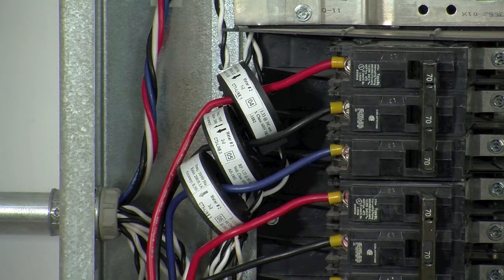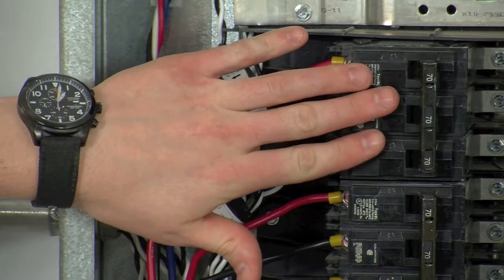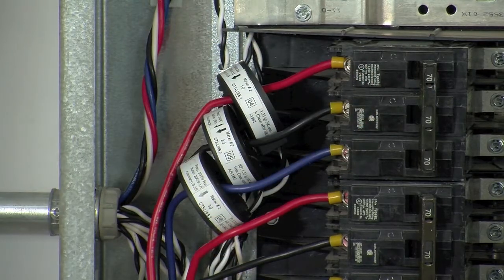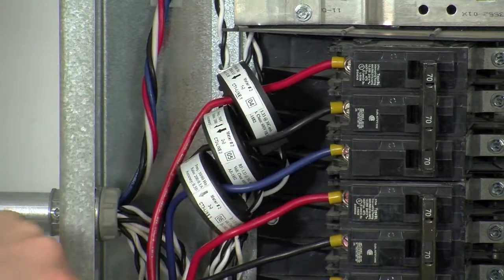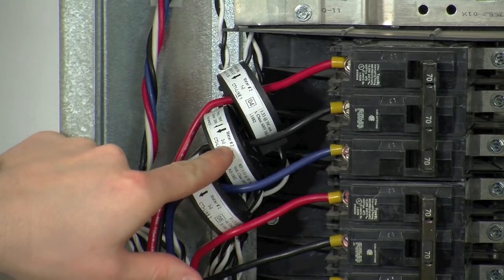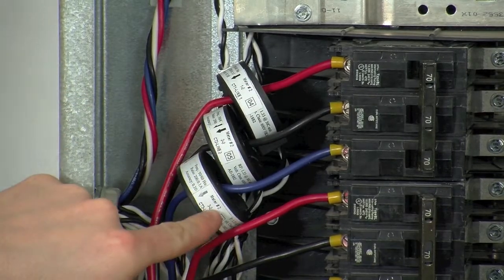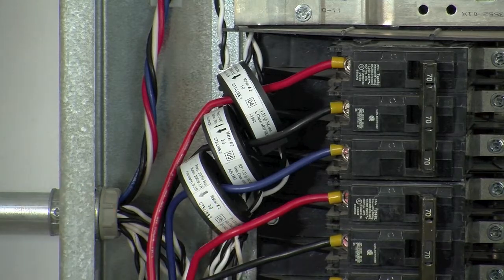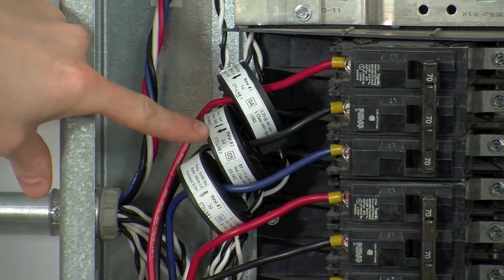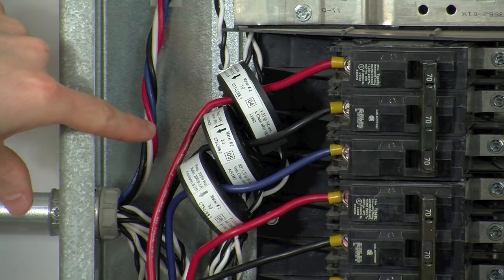Now that we've identified the phasing of the breaker intended to be metered, we can de-energize the panel and install our CTs. So we're going to go ahead and install CT4 on phase A, CT5 on phase B, and CT6 on phase C. Keep in mind that this time the arrow on the label must point out away from the breakers as current flows out from the breaker towards the load.